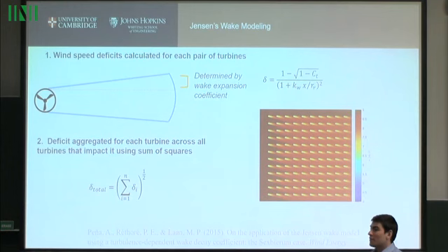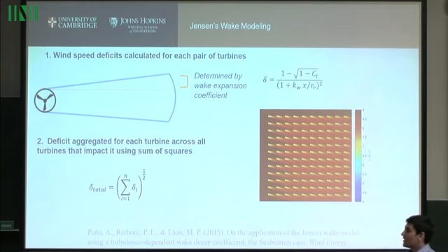However, Jensen's model has been okay at creating on-aggregate wind power output scenarios for a given turbine configuration across different wind speed inputs, across different wind direction inputs. One of the problems, though, is that Jensen's model is often currently not used in conjunction with the true optimal electrical configuration of the layout. So for instance, very simplistically, if you expand a layout, true, you might be producing more power from the individual turbines, but you might not be capturing the true cost to run more expensive, longer, thicker cables between the turbines.